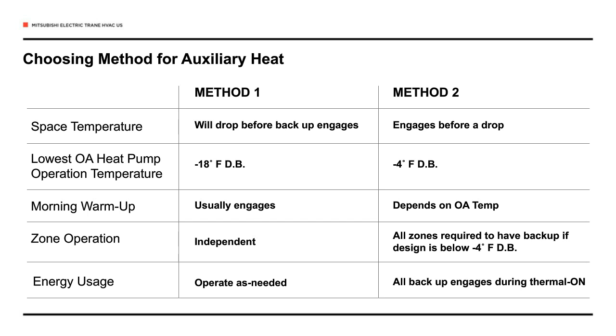So the space may or may not see any degradation in temperature as it's getting colder outside. In other words, you might switch it before you have trouble keeping up from a heat pump heating standpoint. Zone operation, I mentioned earlier, method 1 is independent, so we can put auxiliary heating coils in only our critical spaces. We could also do that in all the spaces. It doesn't necessarily have to be only in some spaces. Whereas with method 2, we want to make sure that all of our zones have backup heat.